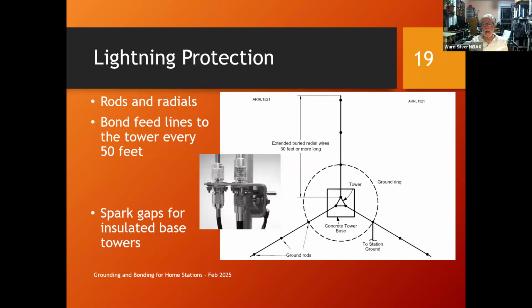It can be as simple as a pair of heavy wires crossing each other, just a little bit apart, so that when there's high voltage, it jumps across that gap. It's like gapping a spark plug. For those of you over a certain age, you've installed spark plugs and set the gap to a few mils, about 0.03 inches. You want to figure out the highest voltage you'll apply to the tower, give yourself a safety margin, and set the gap for that amount of voltage.